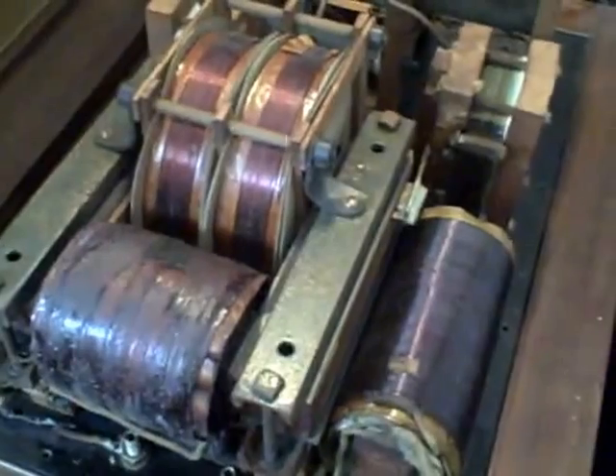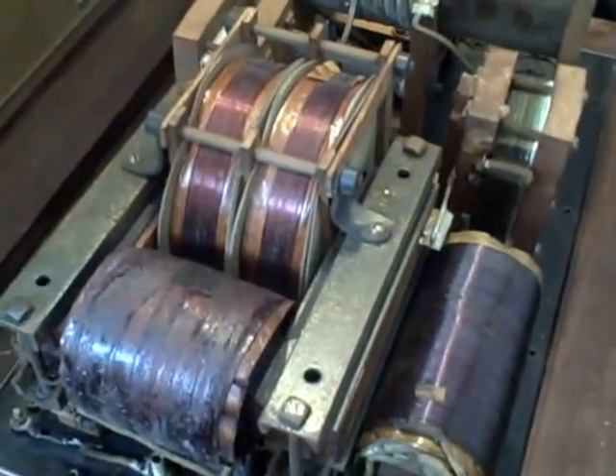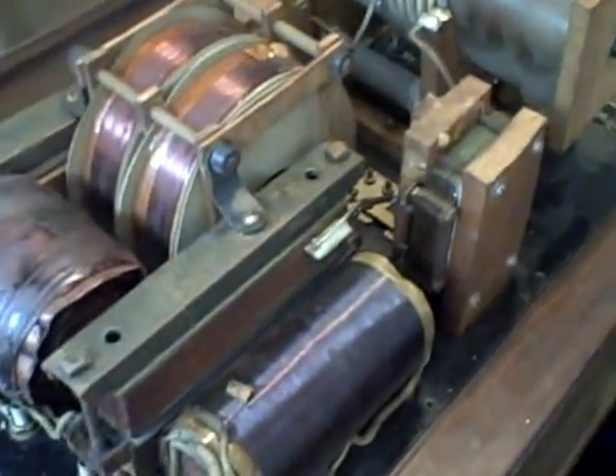They were designed to operate continuously — in the hospital field you may have run these machines 4 or 5 hours at a time, continuously. The fact that they still survive and are still working today is pretty amazing. In this particular model the secondary was only around 3,500 volts, but at a fairly high current. You can see the connections for the spark gap on the other side — it's a 3-series spark gap, very elegant and simple, with a 40-pitch micrometer screw and tungsten buttons. This is the original gap from 1920, and it still works absolutely perfectly.